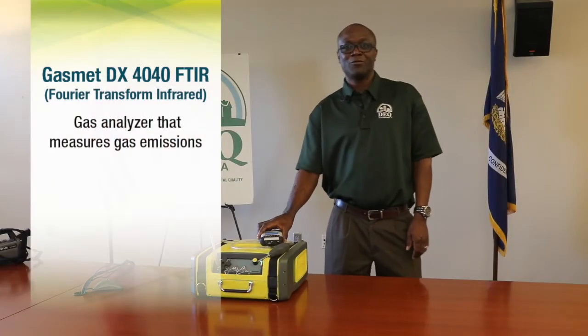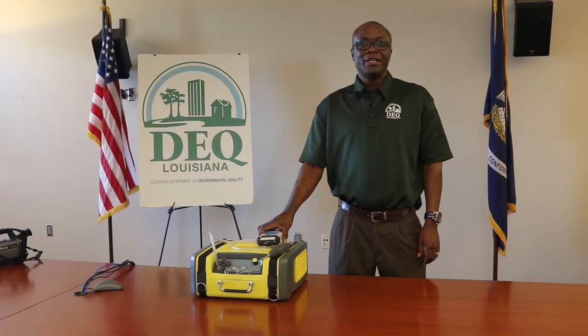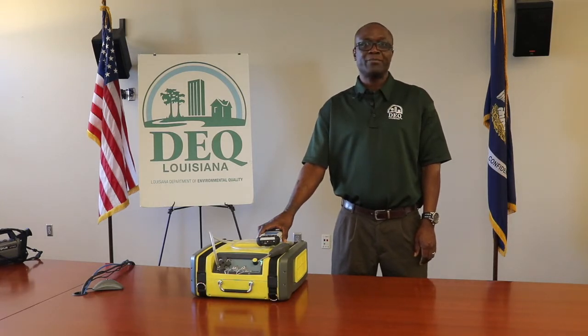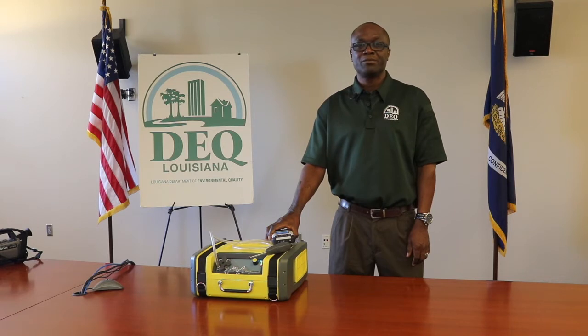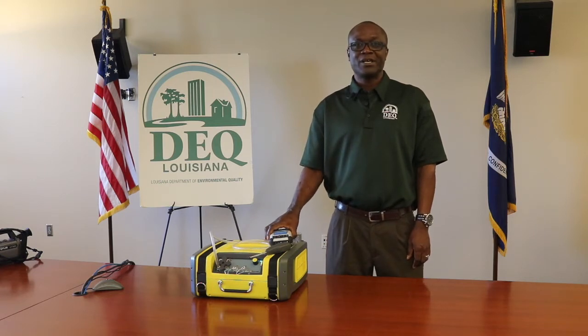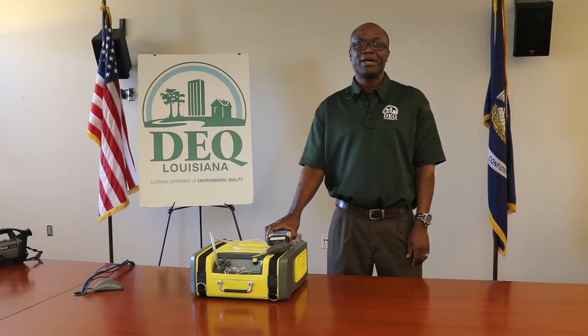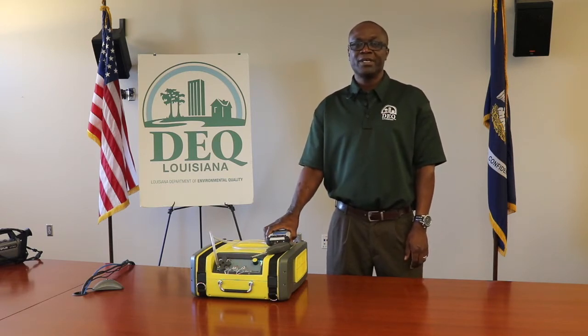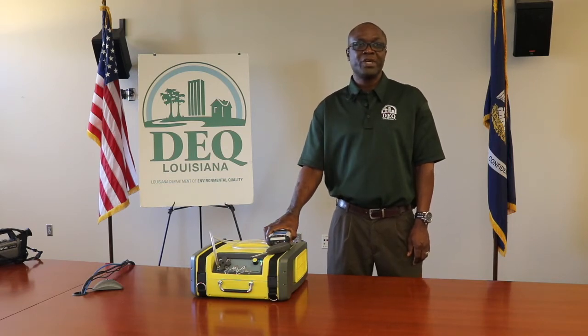This is a Gasmet DX 4040 FTIR gas analyzer. FTIR stands for Fourier Transform Infrared. This instrument is useful for measuring gas emissions in the field at low concentration because of its ease of use, rapid response time, and accuracy. The basic operational process involves infrared radiation passing through a sample; some radiation is absorbed and some passes through or is transmitted. A signal, which is the fingerprint of the sample, is sent to a detector. With this instrument, numerous compounds can be identified simultaneously. It is useful for measuring exposure limits to chemicals set by OSHA. Other instruments are used to measure chemicals at low concentration in accordance with ambient air standards.